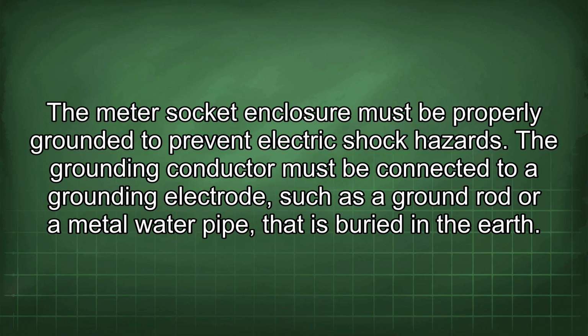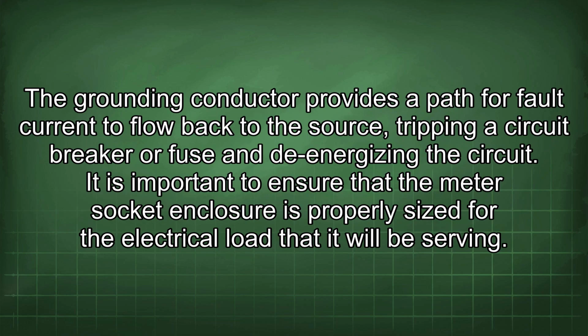The grounding conductor must be connected to a grounding electrode, such as a ground rod or metal water pipe that is buried in the earth. The grounding conductor provides a path for fault current to flow back to the source, tripping a circuit breaker or fuse and de-energizing the circuit.